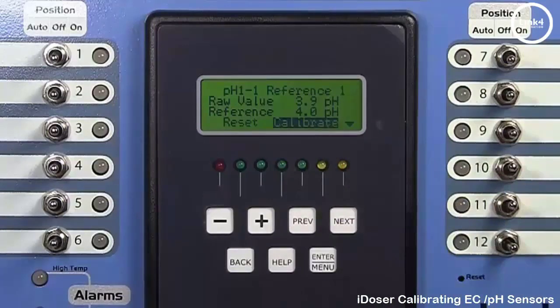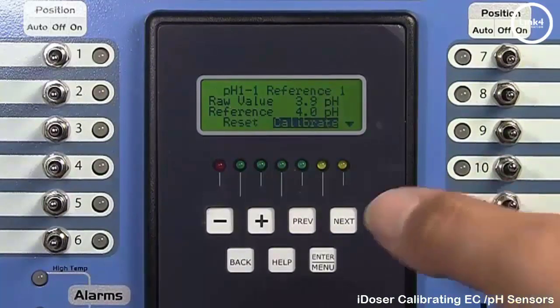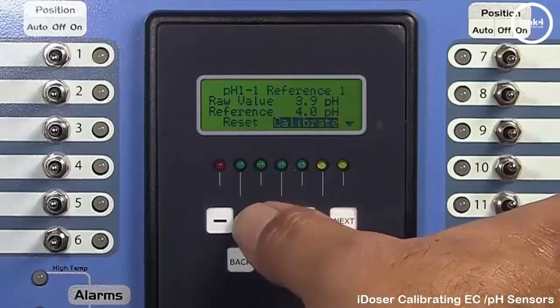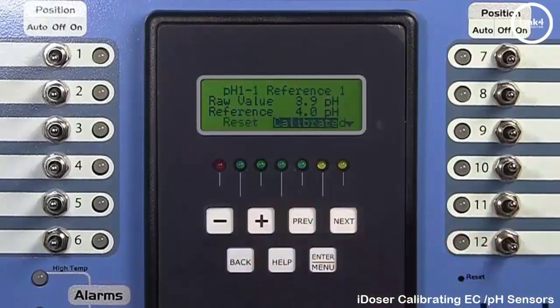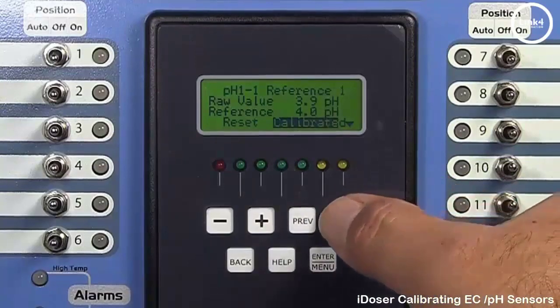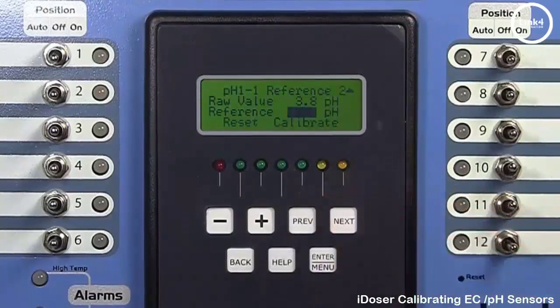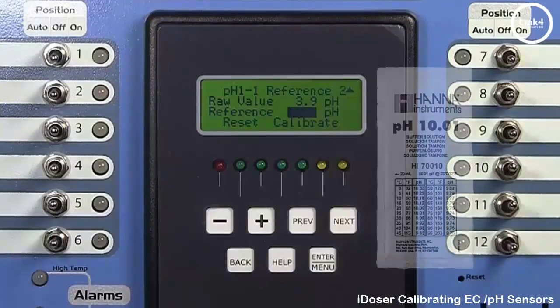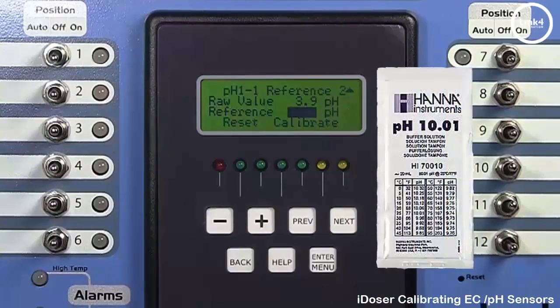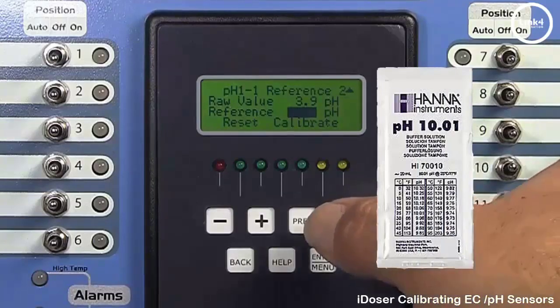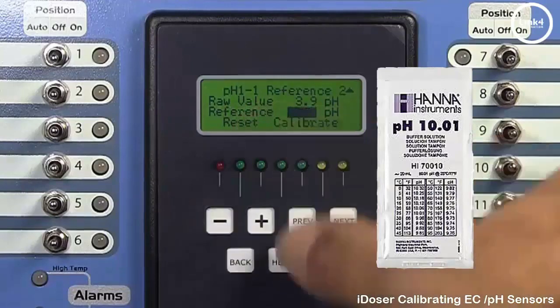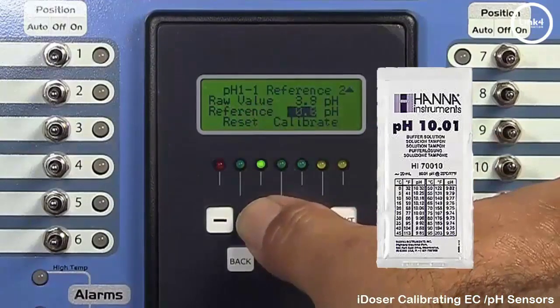Once the value is at 4, just simply hit Next because we know that the sensor has been saturated in the 4 pH calibration solution from the get-go. And just hit plus here to calibrate the sensor. And once it says calibrated, just simply hit Next till we get to the Reference 2 screen. Now here on the Reference 2 screen, we want to utilize 10 pH solution pouch for this second stage calibration. At this field here, we want to make this 10 pH.